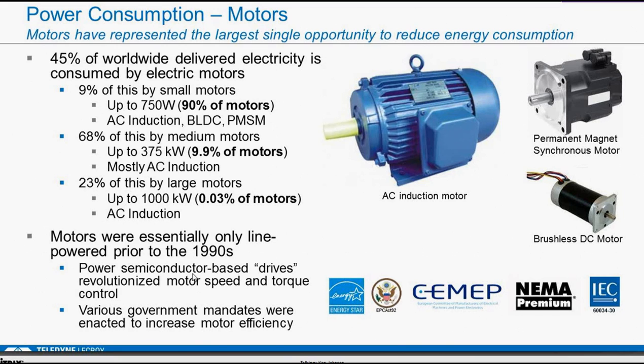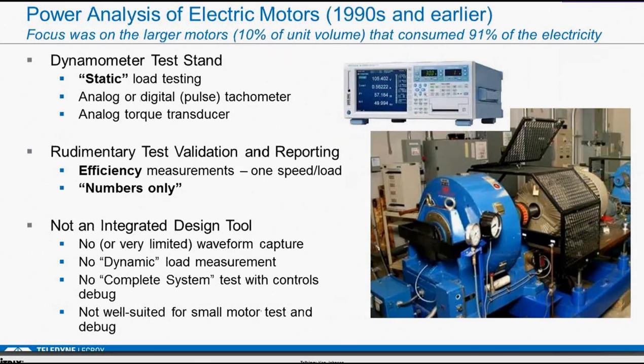So these were essentially only line powered prior to the 90s. And then various government mandates and rules and regulations emerged to make them more efficient, and driving the efficiency were really the use of drives. But historically, they weren't drive-driven. They were just driven off a 50, 60 hertz line. Again, the efficiency of a motor had the ability to really impact the amount of electricity used. So they were tested on a test stand by the manufacturer and certified.